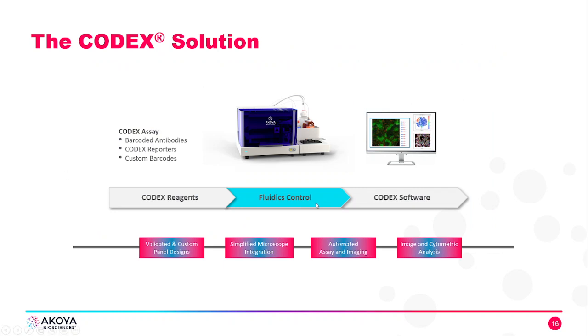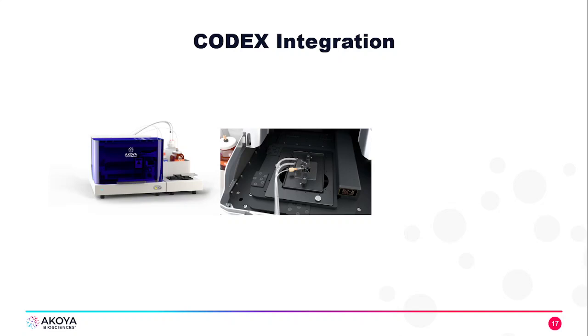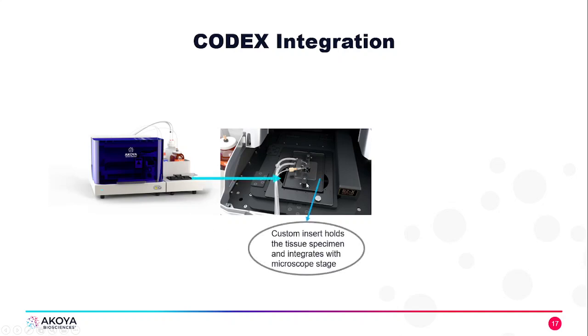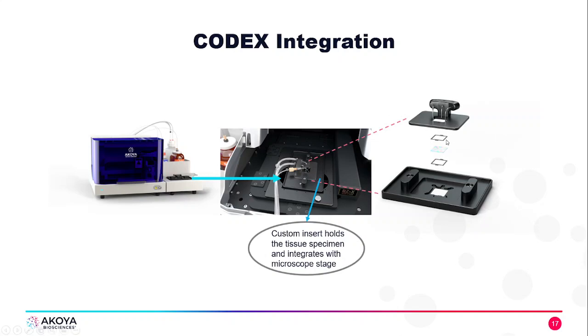Moving on to the fluidics control and the Codex automation, Codex integrates with a microscope to allow for imaging of our tissue section. You can see the fluidic lines feeding to the microscope stage right here. This custom insert holds the tissue and integrates with the microscope stage, where two gaskets are sandwiching the cover slip that will have our tissue on it. That's how Codex integrates with the microscope.